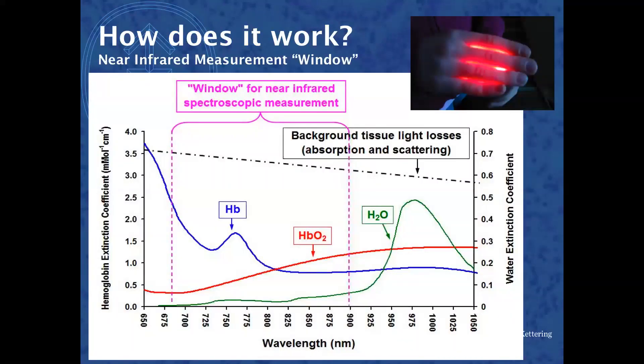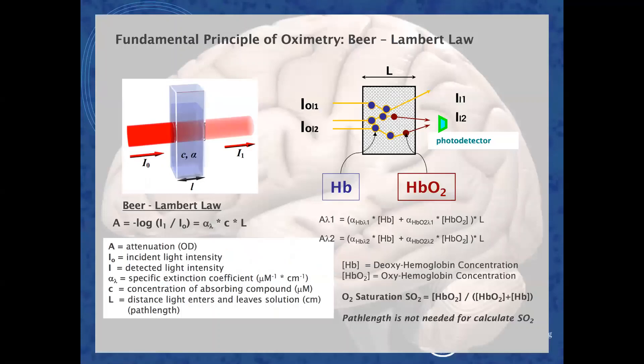The spectroscopic window is between 660 and 900 nanometers, and the spectroscopic fingerprints of oxygenated and deoxygenated hemoglobin are different in this range. Fortunately, there are not many other chromophores in that range to interfere with the photons sent into the patient. The function of oximetry is based on Beer-Lambert's law: if we know the intensity of electromagnetic energy shone into a medium and can measure the intensity after it passes through, there's a change because some energy was absorbed by the chromophore. If we know the path length, we can calculate the concentration of that chromophore.